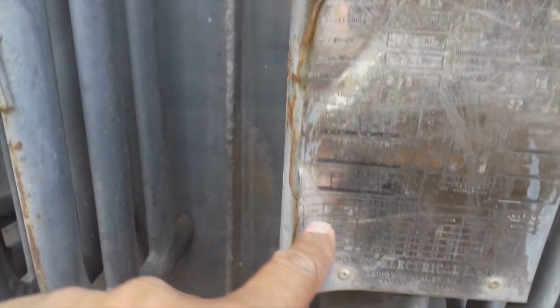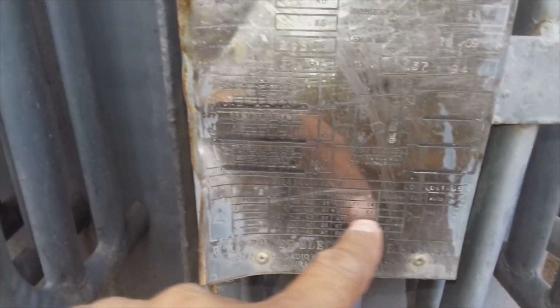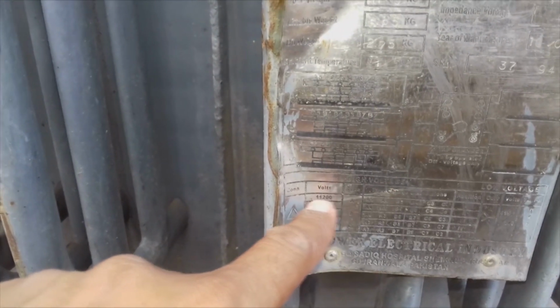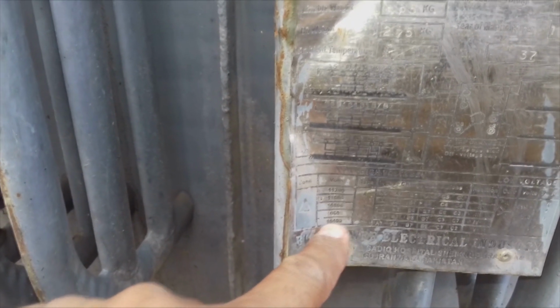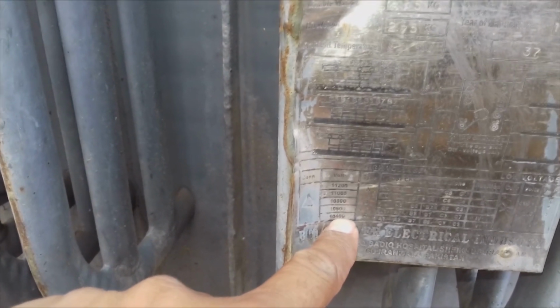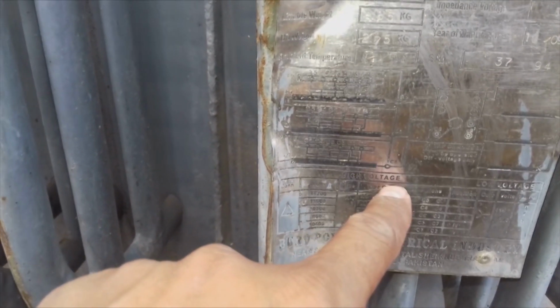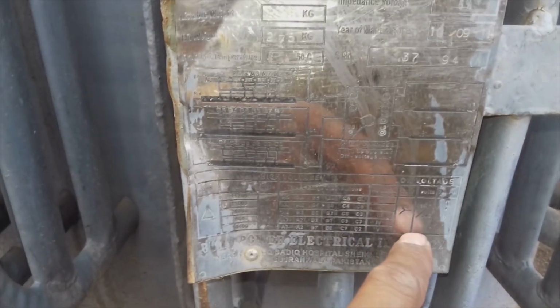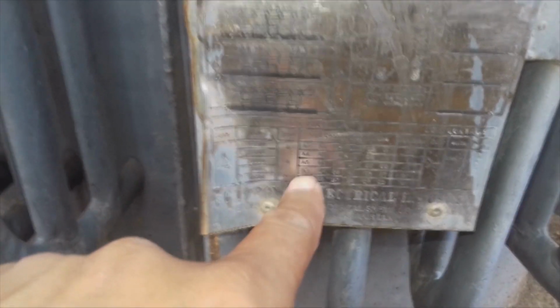So here they have given some details, and here is the detail for the tap changer. The tap changer is actually a device which is connected to the primary side of the transformer, and we can change the voltage through this device. The secondary voltage we can change if we change the tap in the primary side of the transformer. So you can watch my other videos in which I have discussed the voltage changer or the tap changer in detail. So here is the connection detail, which is star in the primary side, and of course the star in the secondary side, and of course the delta in the primary side.